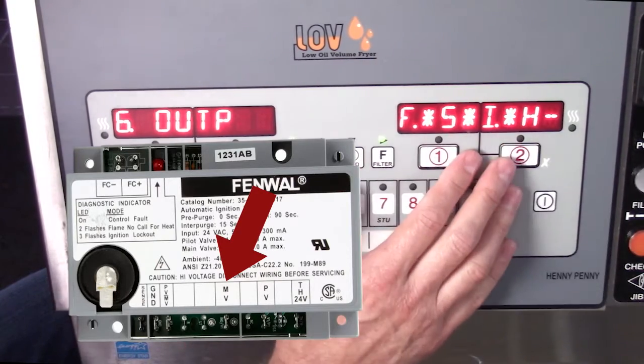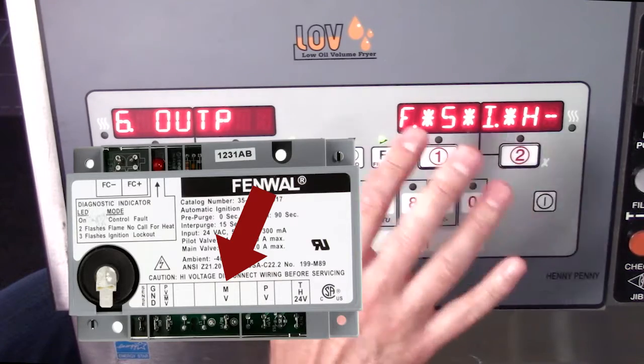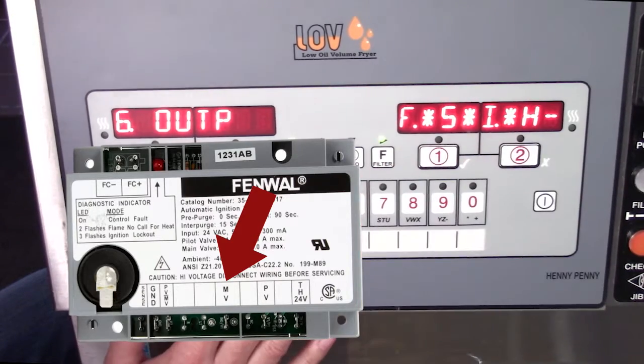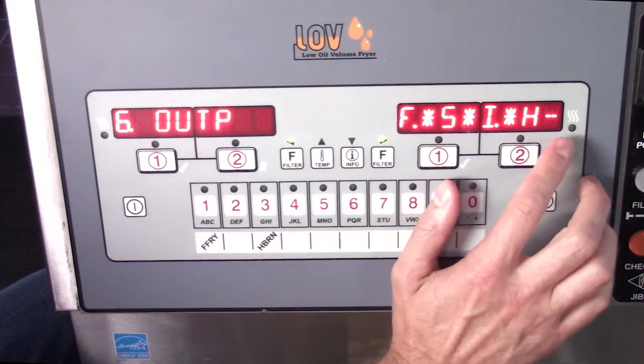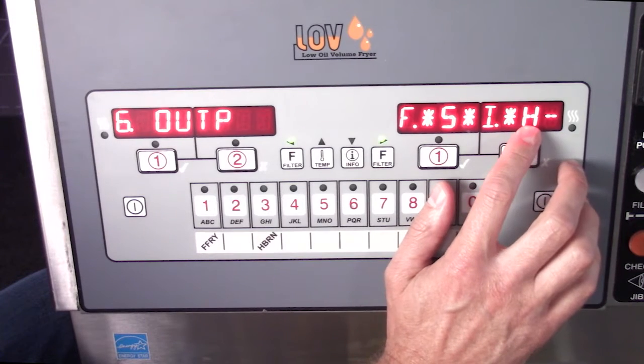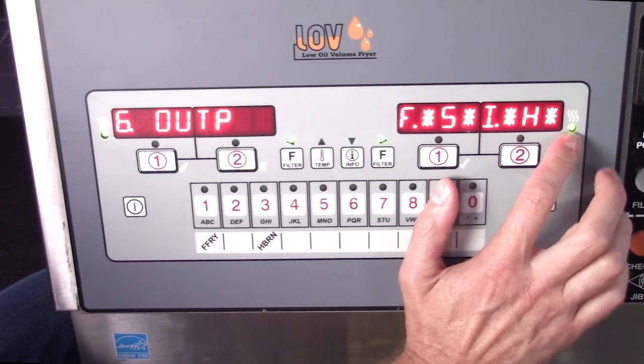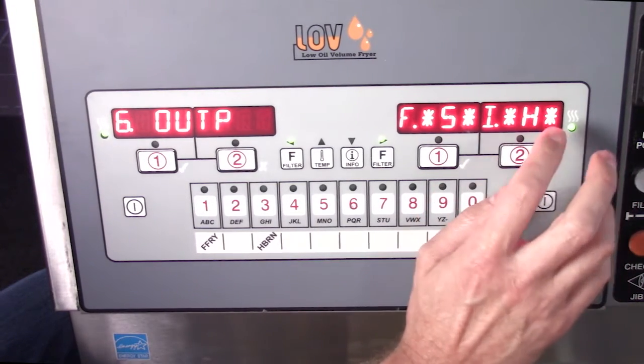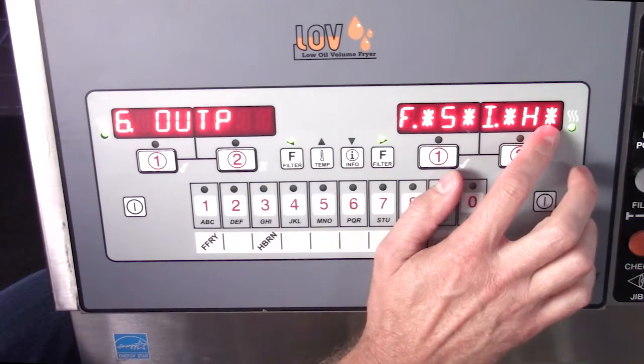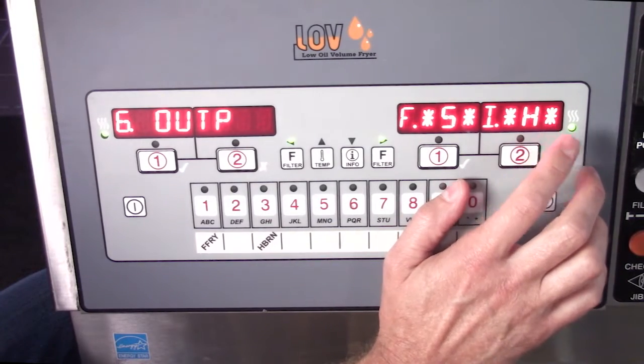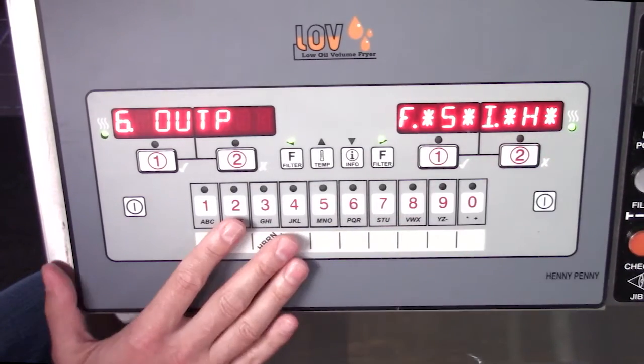And that is my source of power or voltage then that the control uses to send voltage out to my gas valve. And then you'll notice here the H then is going to be for heat or for my main burn, and every time the green LED light comes on, then I get my little asterisk beside here telling me that it's closing the relay on the board and allowing the voltage then to go out.